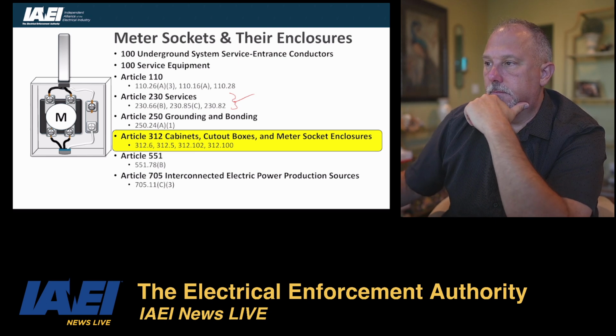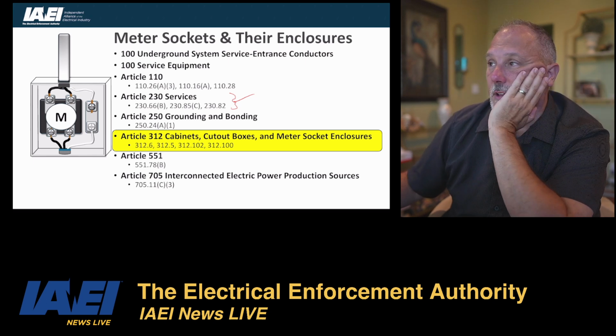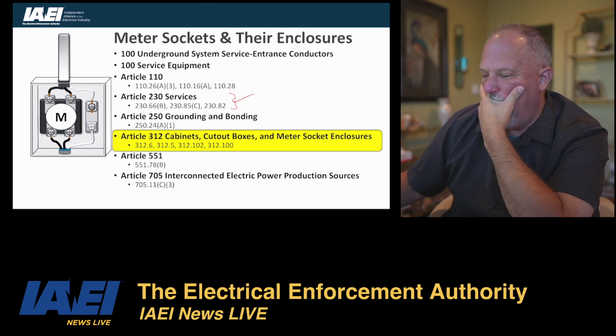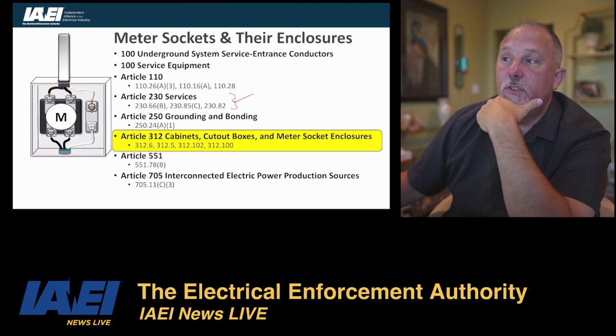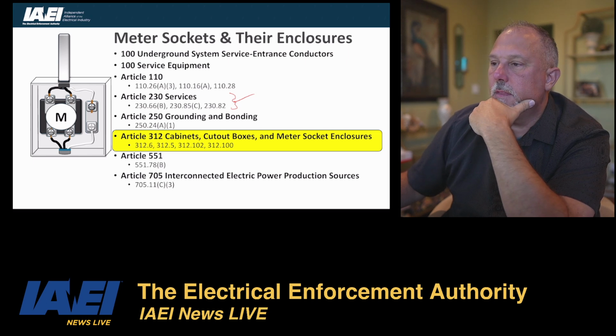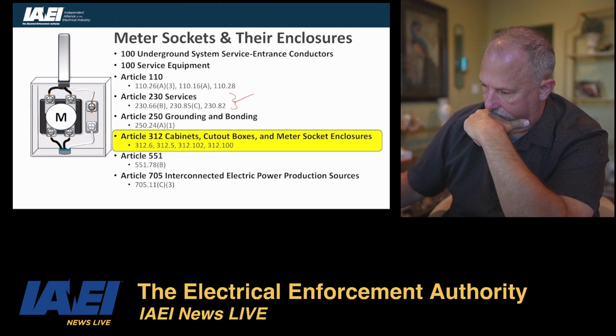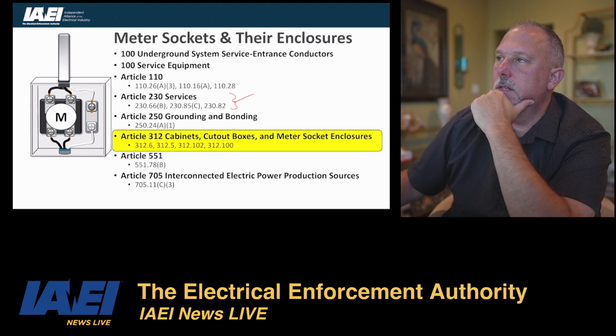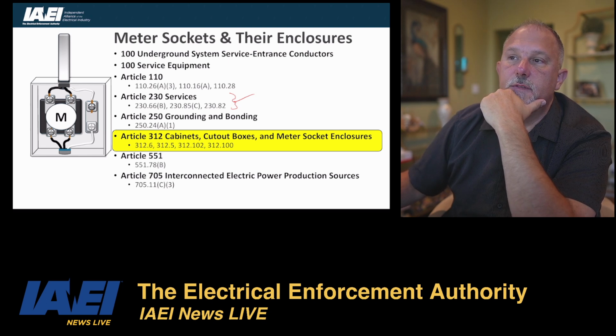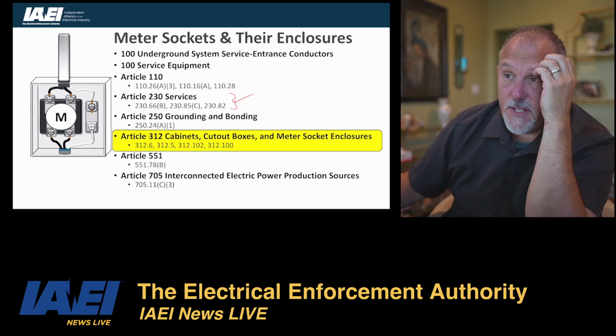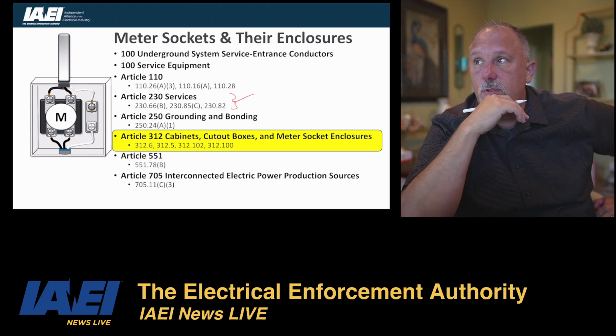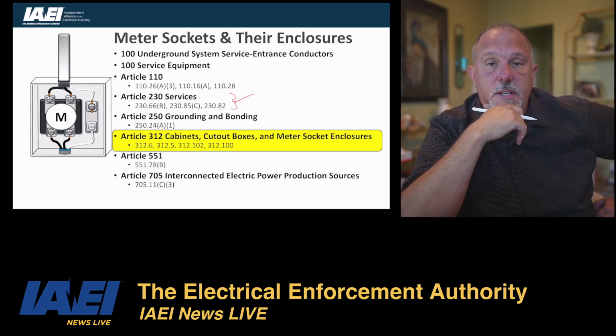Now, they also talk about a meter-mounted transfer switch. That's also permitted on the line side of the service disconnect. And we already talked about the change I was suggesting with item 5. I think it's listed item 5. Now, the other section, 230.85. We may have moved some things around. Yeah, 230.85 is the emergency disconnect. I'll tell you what we did in the 2026 code. We are going to require the service disconnecting means to be on the outside of the house.